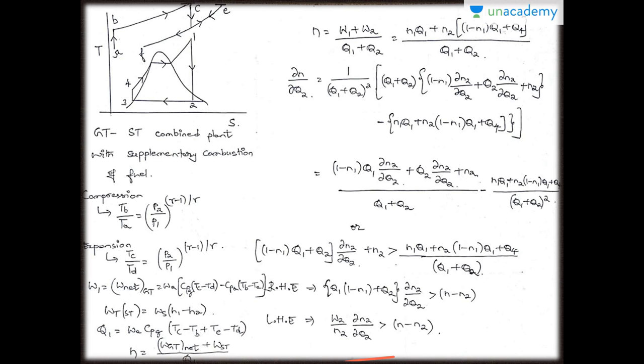With additional firing of fuel in the HRSG, the power output of the steam cycle as well as its efficiency increase, and so the increase in overall efficiency diminishes. Therefore, supplementary firing is becoming less and less attractive. Generally, it is more profitable to burn the fuel in the combustor of the gas turbine plant itself since the heat is supplied at a temperature higher than that in the steam cycle. For the compression process of air, the equation is TB/TA equals (P2/P1) raised to (gamma minus 1)/gamma, where gamma is 1.4. For the expansion process, it is TC/TD equals (P2/P1) raised to (gamma minus 1)/gamma.